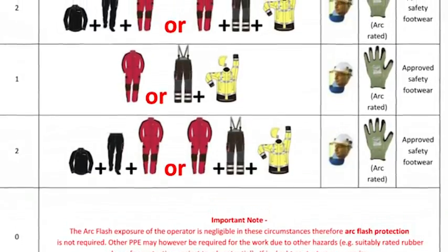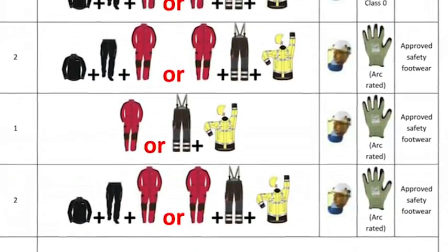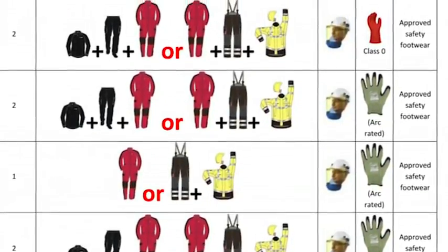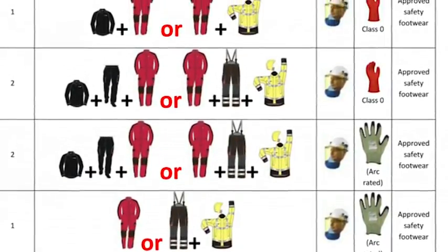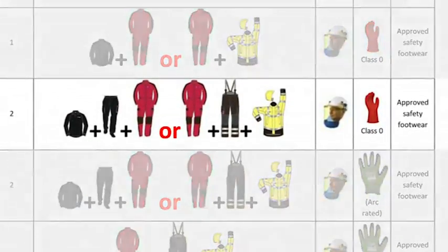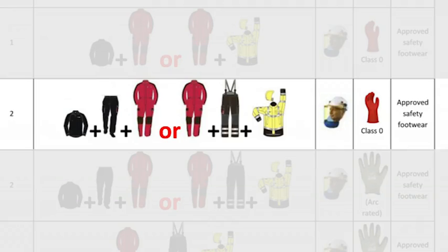For work, testing or operations on LV mains, including link boxes, feeder pillars, cables and service terminations above 100 amps, a 2-layer combination is needed. Wherever a 2-layer solution is required, this can be provided by your arc flash shirt and pants, worn with your coverall, or coverall and your wet weather clothing. It's your choice.